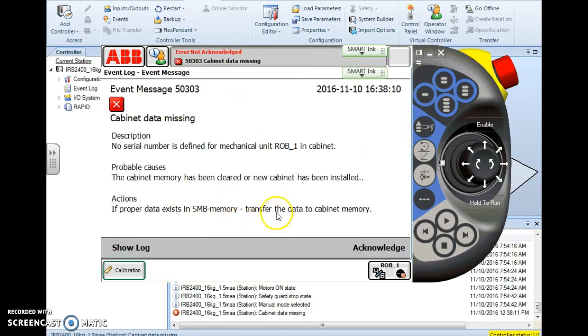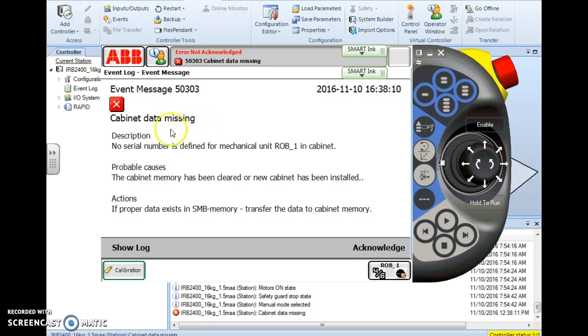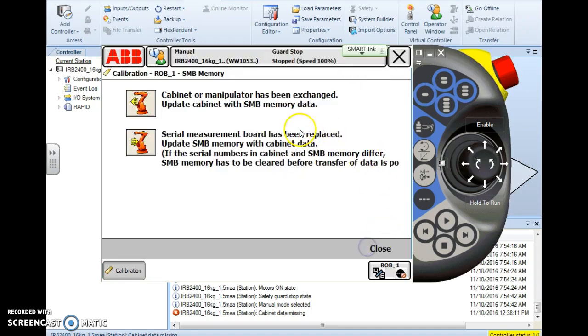And at that point, as long as you're connected to a cabinet, you shouldn't get this error. But if you get this error, that means not only your SMB is bad but your cabinet data is bad too. But if you have a functional cabinet and you know the SMB was bad and you update to it, then it should just pop up a window saying update successful. So it's a pretty quick and easy process and it sure beats running the fine calibration process which can take an extended amount of time.